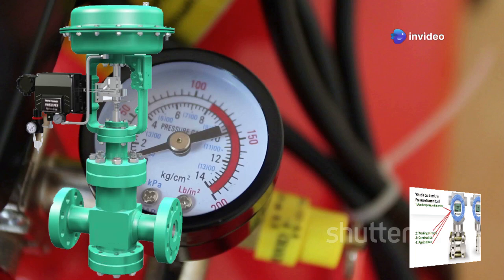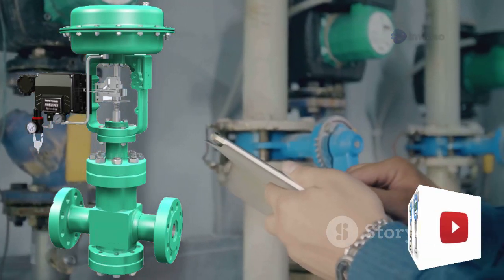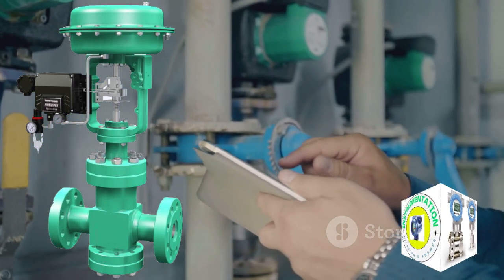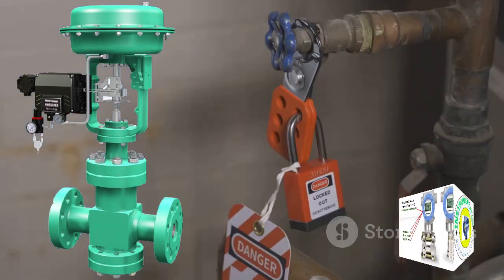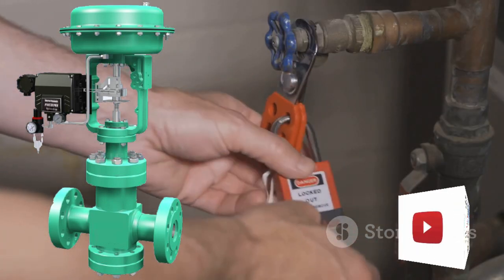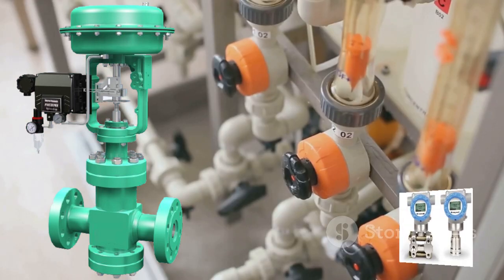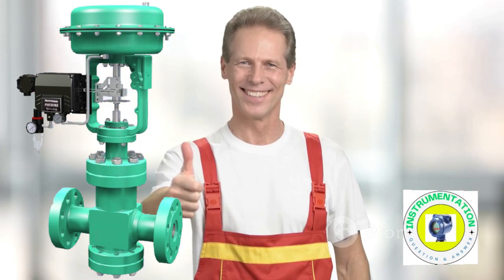I like to run a ramp or step test, move from 0 to 100 in steps, and make sure everything's responding as expected. Once satisfied, remove your lockout, tag out, and return the valve to service. And that's it. You're calibrated and good.